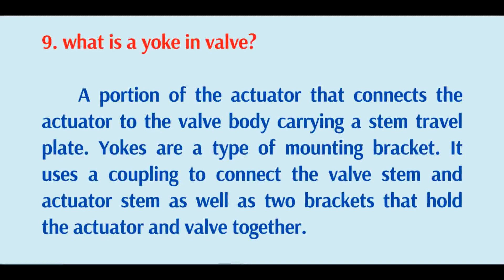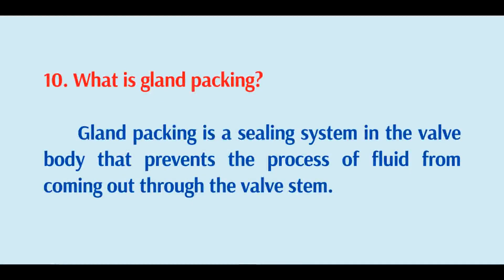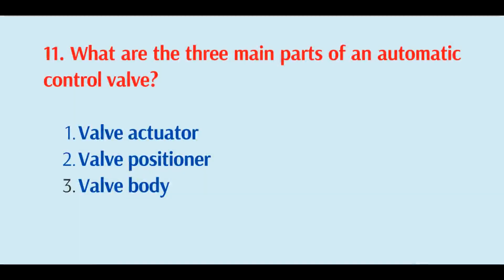What is a yoke on a valve? A portion of the actuator which connects the actuator to the valve body, carrying a stem travel plate. Yokes are a type of mounting bracket that uses a coupling to connect the valve stem and actuator stem, as well as two brackets that hold the actuator and valve together. What is gland packing? Gland packing is a sealing system in the valve body which prevents the process fluid from coming out through the valve stem.